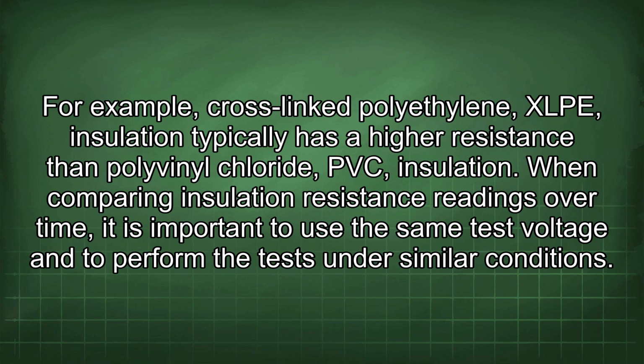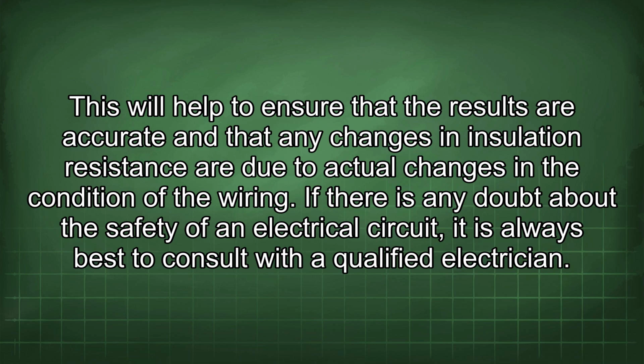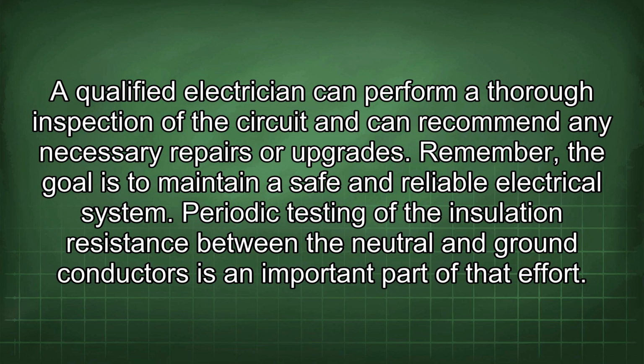When comparing insulation resistance readings over time, it is important to use the same test voltage and to perform the tests under similar conditions. This will help to ensure that the results are accurate and that any changes in insulation resistance are due to actual changes in the condition of the wiring. If there is any doubt about the safety of an electrical circuit, it is always best to consult with a qualified electrician. A qualified electrician can perform a thorough inspection of the circuit and can recommend any necessary repairs or upgrades. Remember, the goal is to maintain a safe and reliable electrical system.